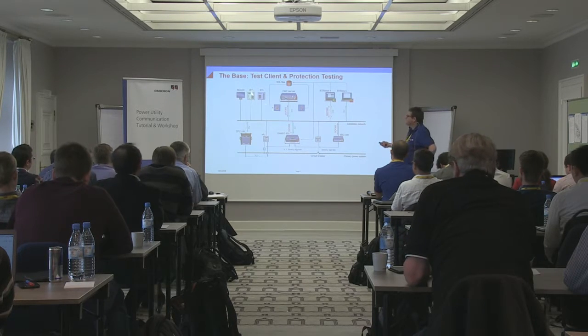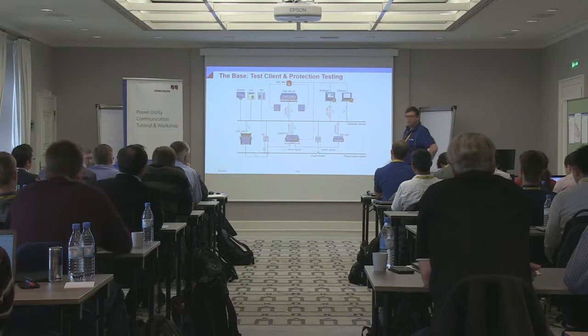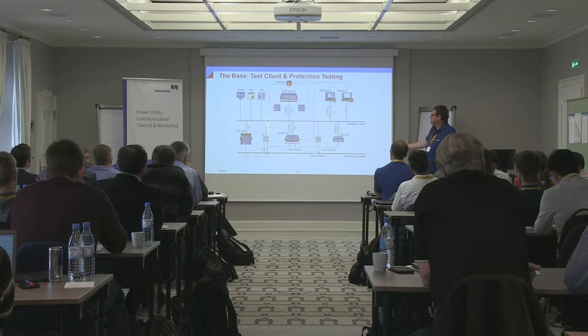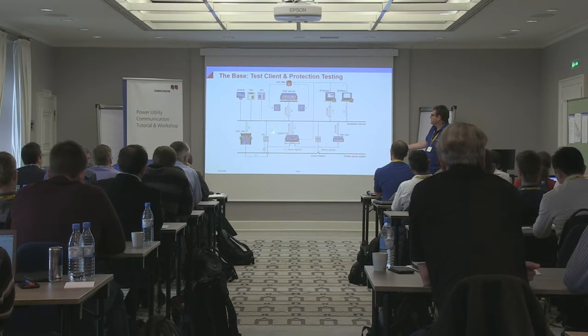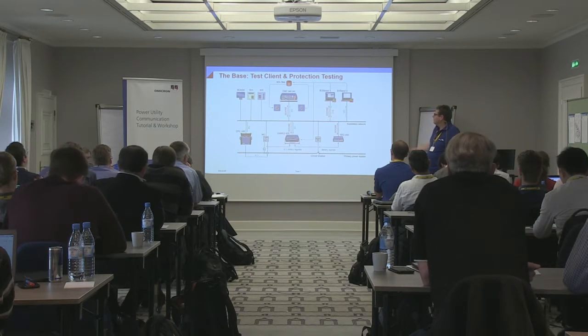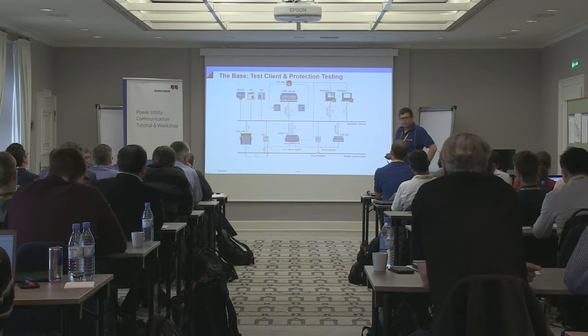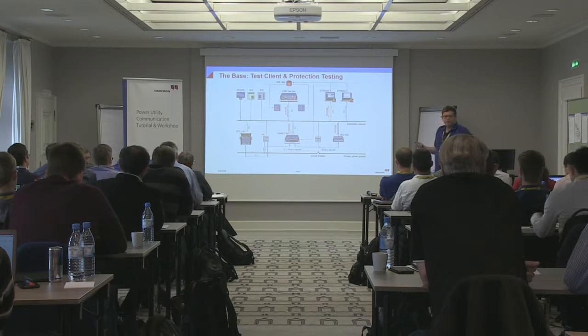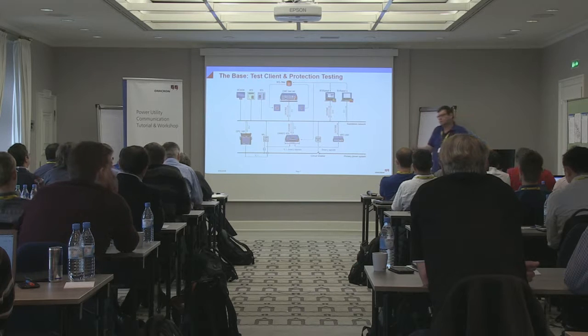So we have now GOOSEs issued here by the protection devices, for instance. It might be that there are also merging units publishing the sampled values here over the network. And now we want to start there with the testing. Now we have the different possibilities. If we are working with GOOSE, then we receive it everywhere free of charge, and we can use it also for testing, for recording, for supervision.